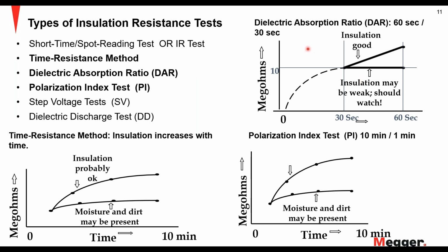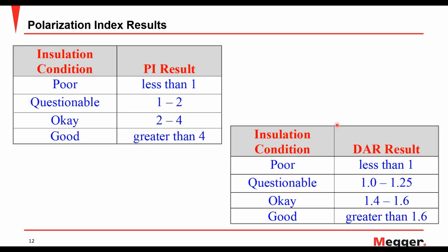And these are all the different graphs that you get from all the different kinds of tests. Your PI test, your DAR test, 60 seconds to 30 seconds ratio, and this one is a good insulation condition determination. If your PI test result is less than 1, then you know that insulation condition is poor. 1 to 2 is questionable, and so on and so forth. Similar for a DAR result, anything that is less than 1, definitely it's a poor condition on the insulation.